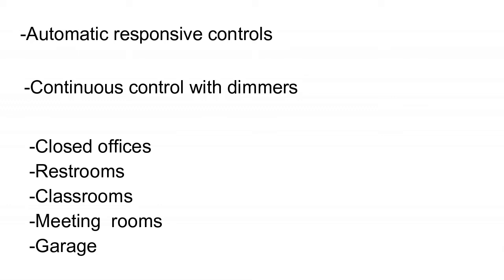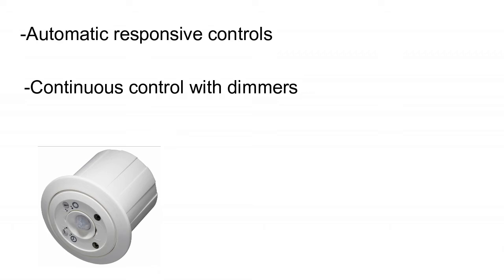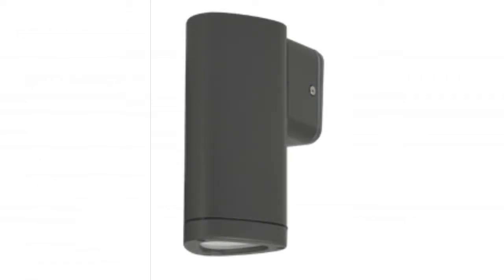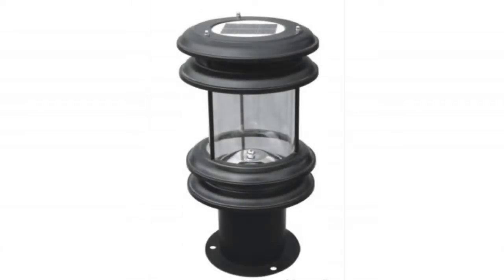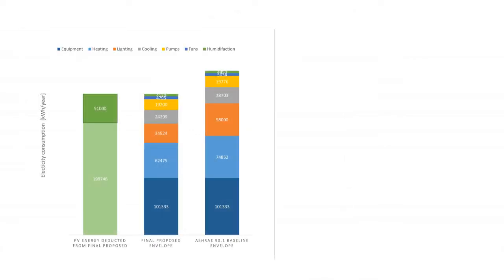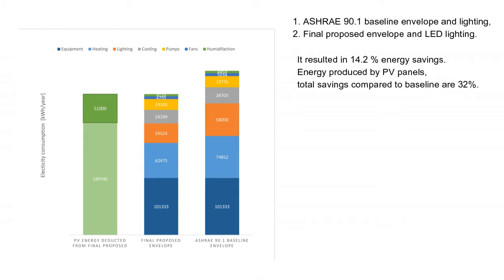Relatively smaller spaces and rather discrete occupancy profiles, such as enclosed offices, restrooms, classrooms, meeting rooms, and emergency vehicle garage, will have ceiling-mounted occupancy sensor devices to shut off lighting after the space is unoccupied longer than 10 minutes. Facade lighting consists of wall-mounted LED lights of 3-watt power input. Decorative lighting consists of LED solar lanterns which recharge during the day and are completely independent from the grid. To determine building performance, 2 separate simulations were done for the selected HVAC system.